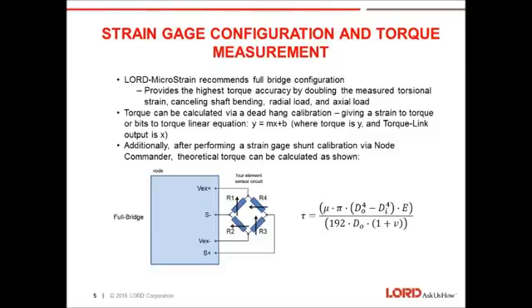Additionally, the customer could do a theoretical torque conversion, where as long as they perform a strain gauge shunt calibration via Node Commander, they can input the output strain into the equation shown here on the chart, which requires knowledge of shaft diameters and shaft material properties, such as the modulus of elasticity and the Poisson ratio.